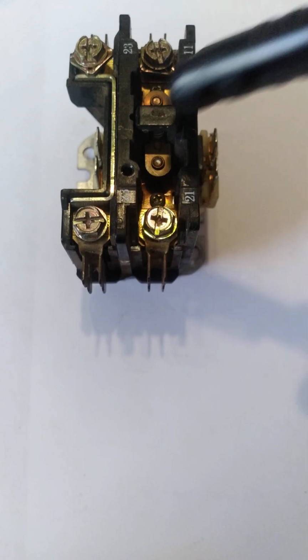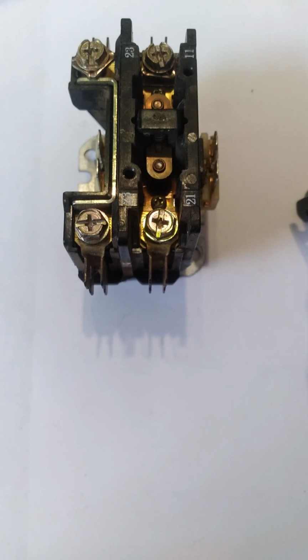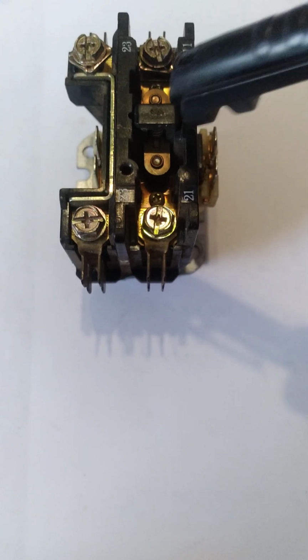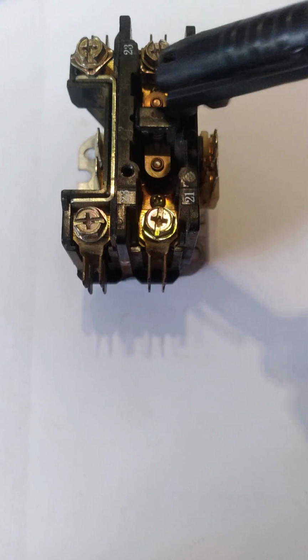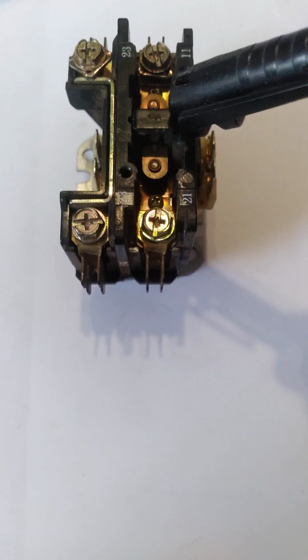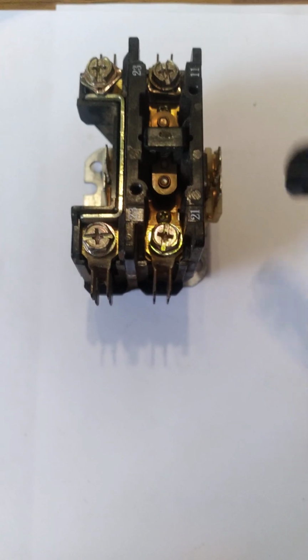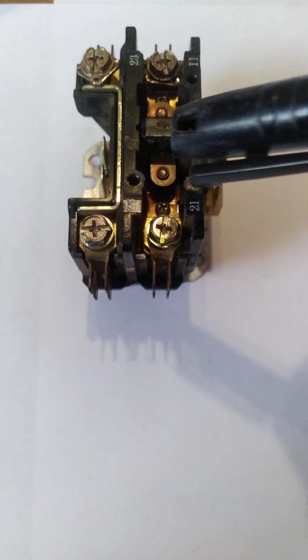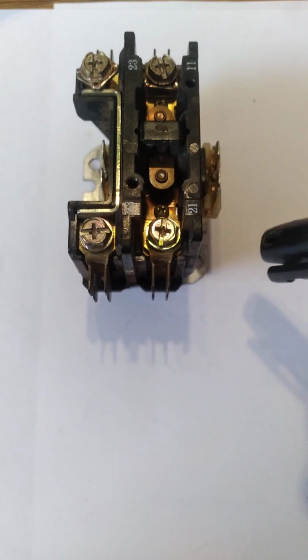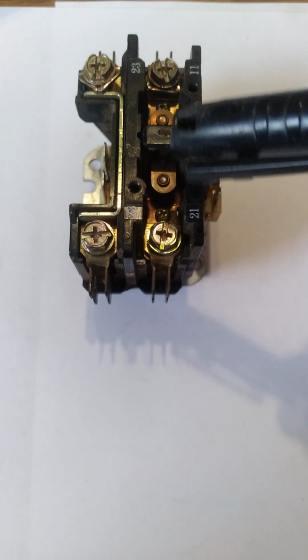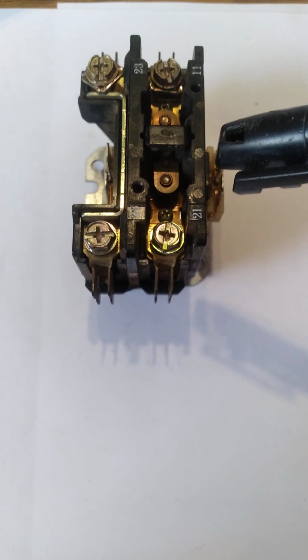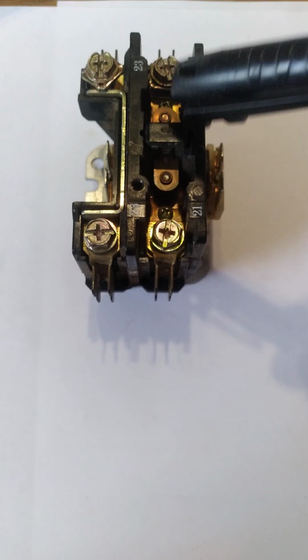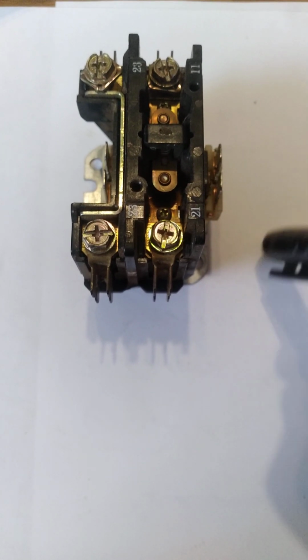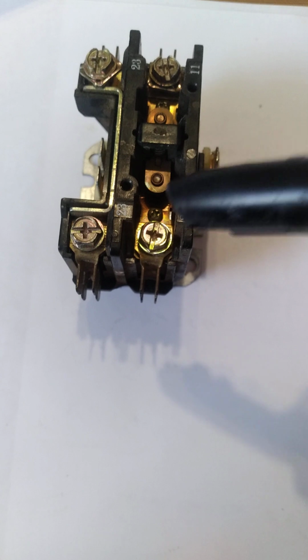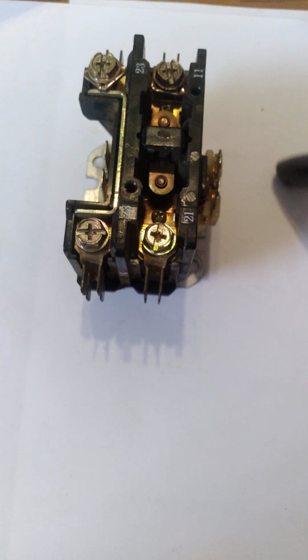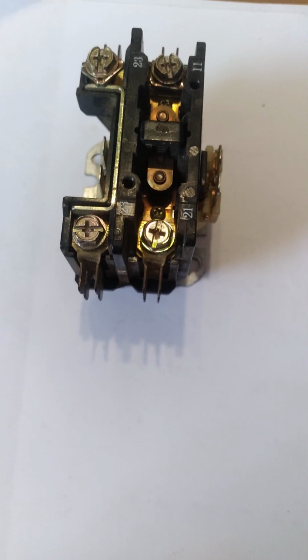However, sometimes, and one other issue with these, be aware that for some reason ants love to get in these. So these contactors can go bad. They can get ants inside of them, multiple reasons. They can get pitted and welded together. So anyway, this contactor will allow low voltage to energize, allowing high voltage from this side to this side. It's that simple, and that would be enough voltage to run your compressor and condenser fan motor.